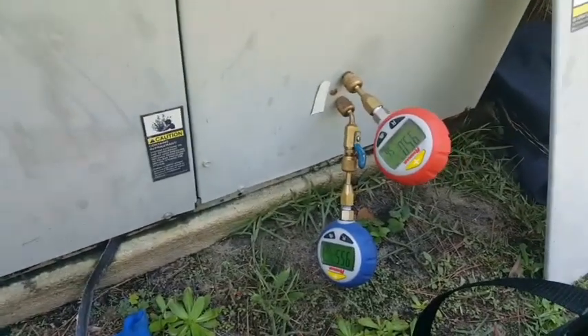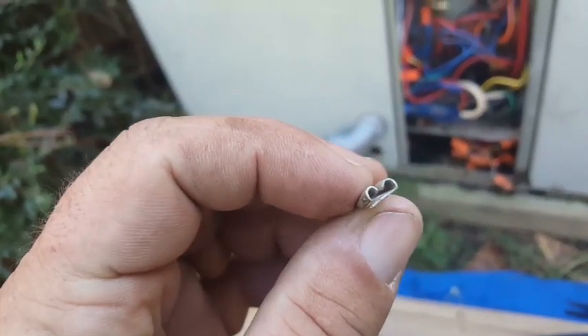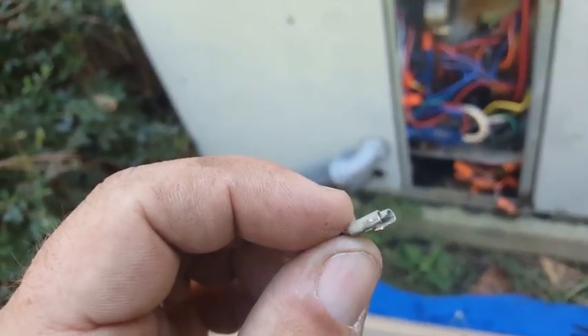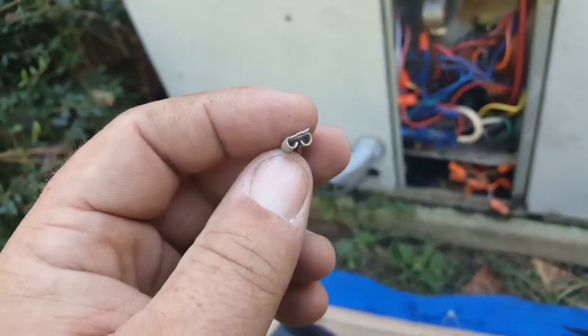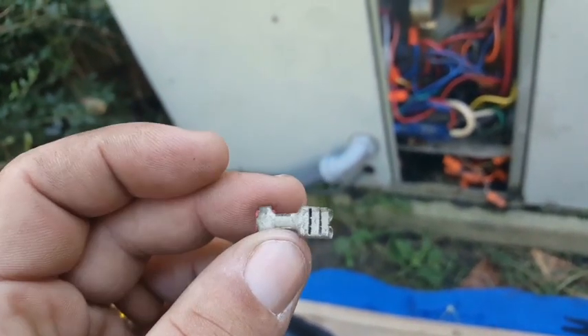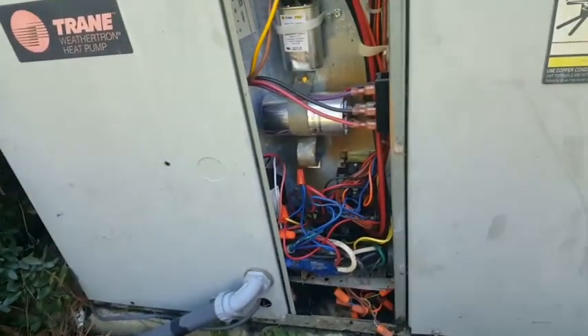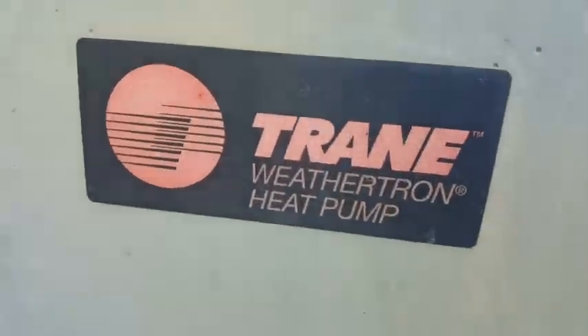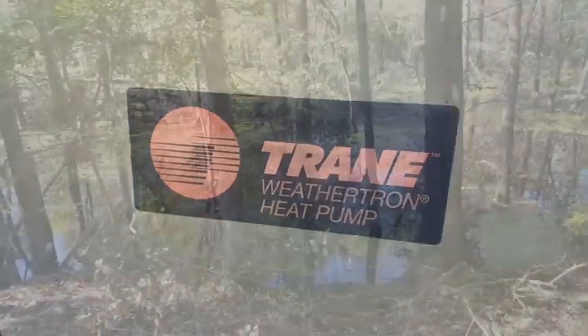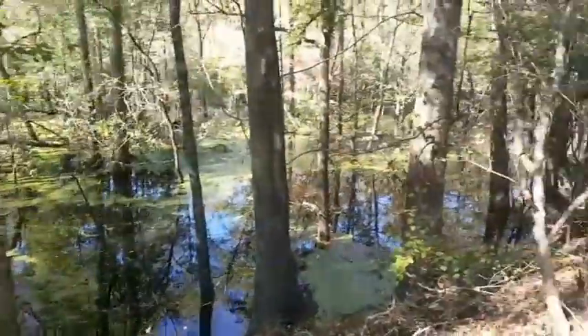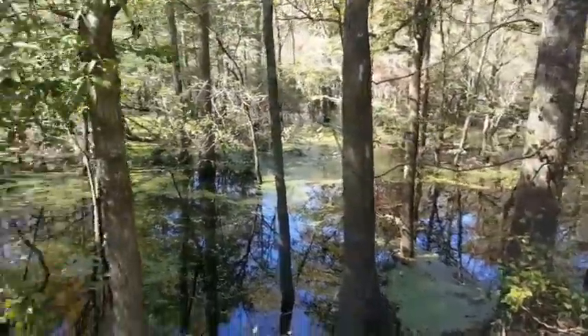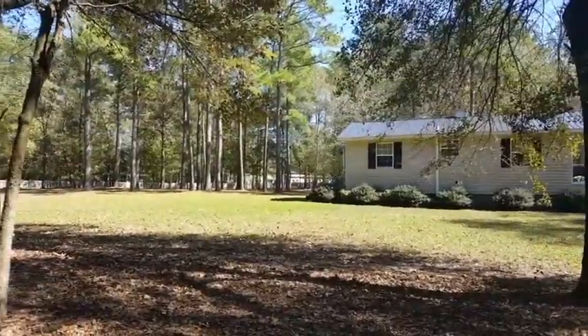And I noticed the compressor wasn't running, and I looked down here and the red wire had fallen off the contactor where I had that new stake-on, because the stake-on actually broke. I didn't see that. Oh, old stuff. What are you going to do? So I remade that connection, and we're going to fire it up again, and hopefully she runs like a train. Right, Trane guys? Yeah, whatever. Well, I decided to kill my 5-minute delay before the machine comes back on. You see the machine's up here on the left side of that house there.